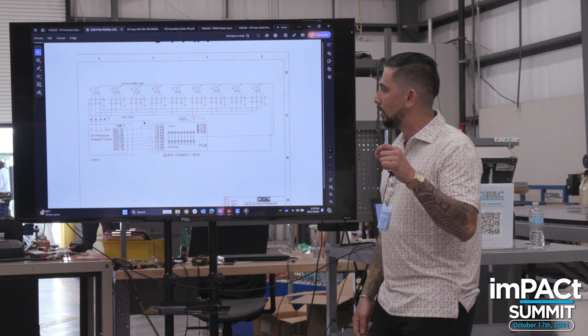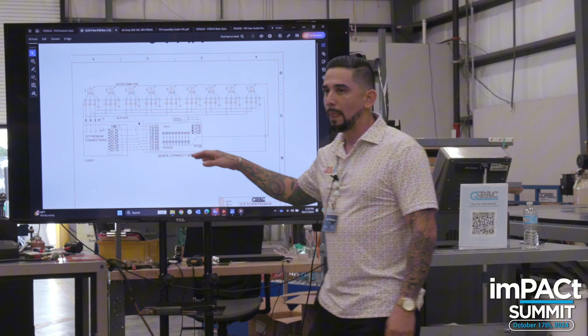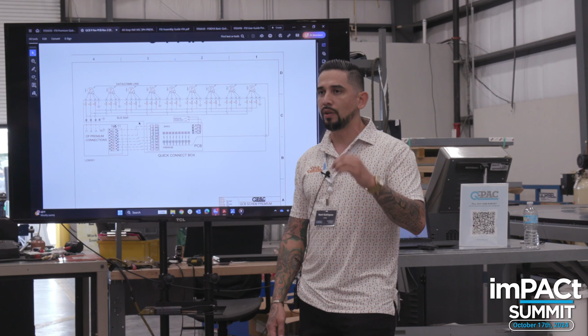This does not... you need the low voltage to help them run. So if the safety is not made, you will never get power to the motors. So I get a call a lot about, I don't have power to the motors, I can't get it to run. They don't land that safety circuit, that DI1 to 24 volts. So that's what engages your M1 contactor, and then that releases the power to your motors.